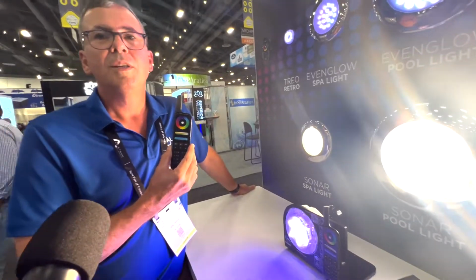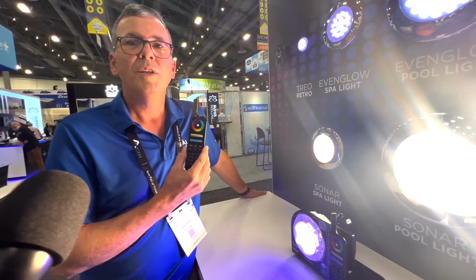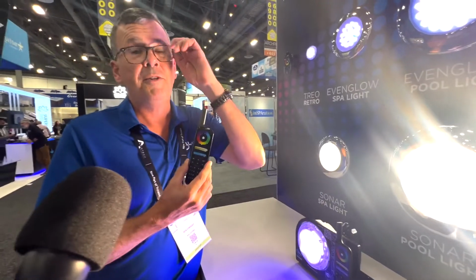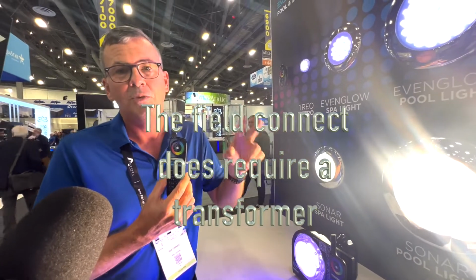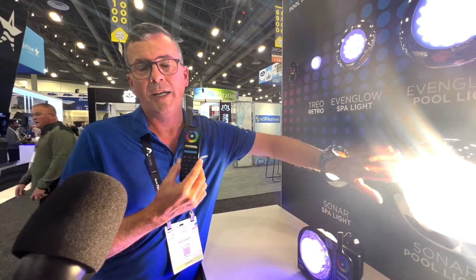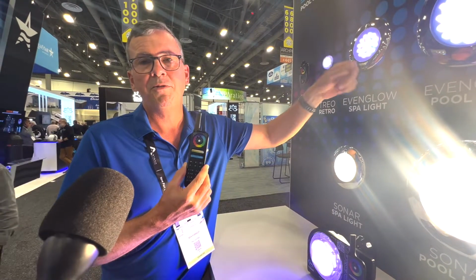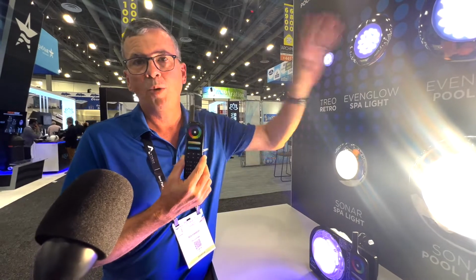So you can replace a typical light, but they're not high voltage though, they're low voltage. That's right. The Field Connect cable that we're using to connect to that existing 2-wire cable is UL approved, but only for low voltage. So if you are replacing an incandescent bulb in an environment that's 110 volts, you'll also need to go to the other end of the cable where it comes from the breaker, pull it out and put either a 12 volt AC, 12 volt DC or 24 volt DC transformer in there and convert the whole line to low voltage.